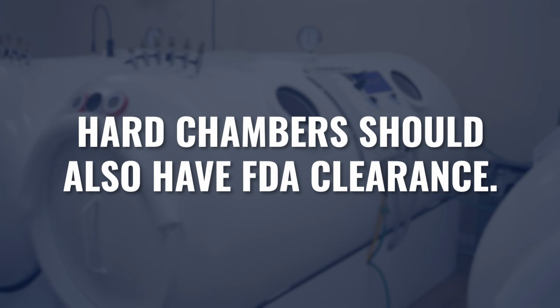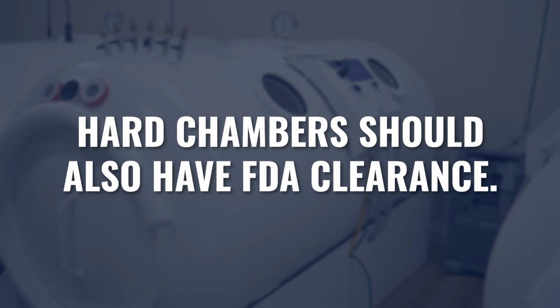And if your equipment is ASME and PVHO approved, it will have a plaque, a metal stamp on the chamber with the PVHO approved mark. Both hard chambers and soft chambers should also have an FDA clearance. And if your equipment does, then your manufacturer would be able to supply you with an FDA clearance letter showing that the FDA has approved this equipment for use. This is important because there are build to standards that these chambers need to meet or exceed in order to make sure that the equipment that you're utilizing is safe.